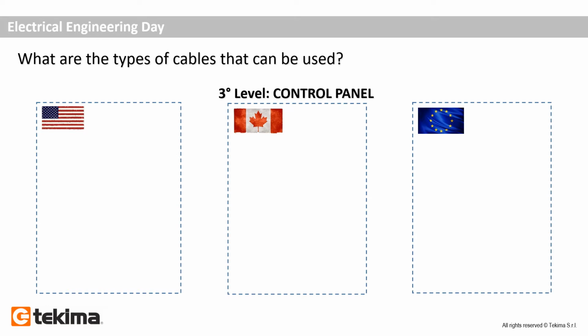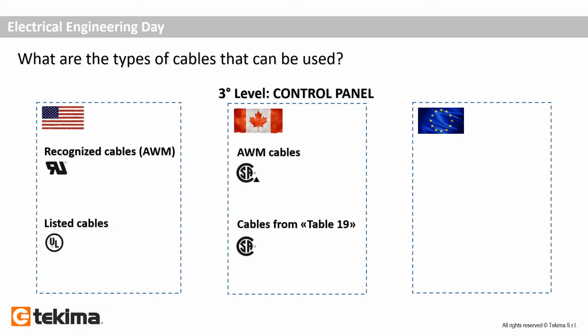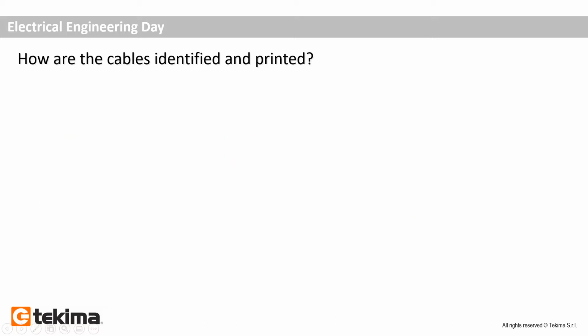Electrical panels. Same options for electrical panels. AWM cables and listed cable are both admitted in the US and in Canada. In this case, without any special requirement. Again, for the EU mark, all the third-party certified cables are recognized. How can I verify the certification of the cable and for which market it is compliant? Are there any marking rules for the cable?